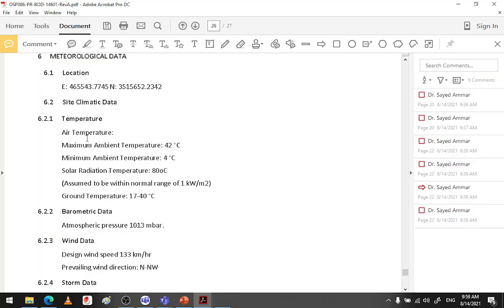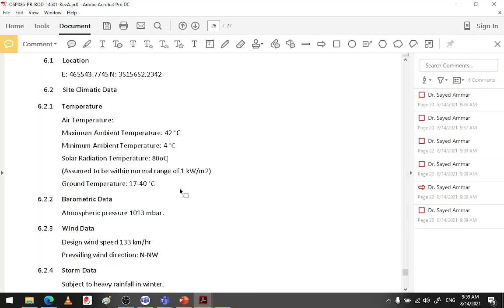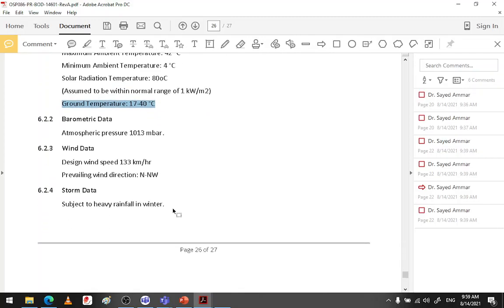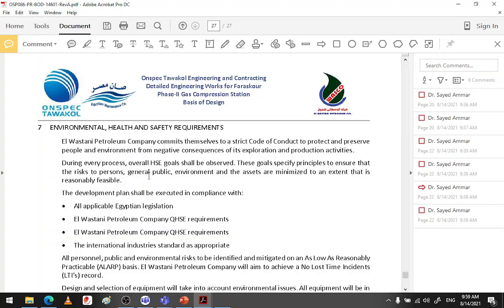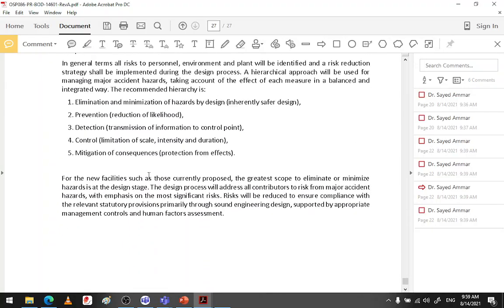Meteorological data, which is most important for us as process engineers: maximum ambient temperature, as we said, minimum ambient temperature, solar radiation of 1 kilowatt per meter square. It will be very helpful during the flare dispersion calculation. Ground temperature will be between 17 to 40 Celsius. Wind speed is for the civil people, nothing else for the basis of the design. Let's close it.